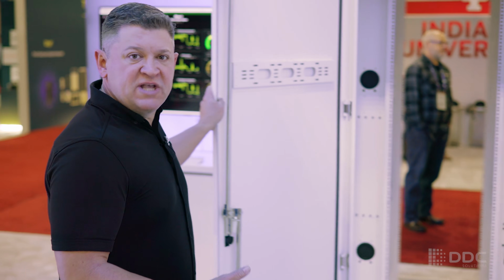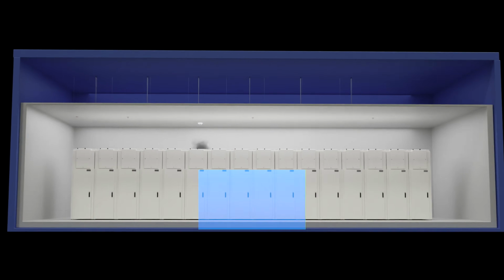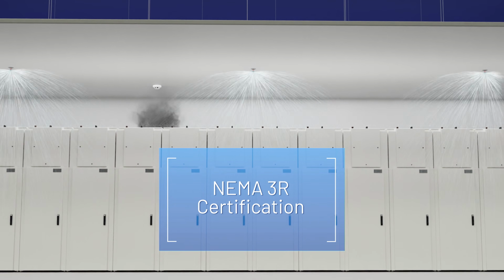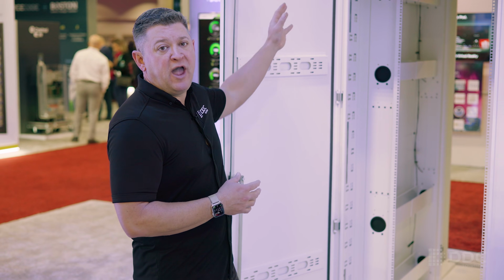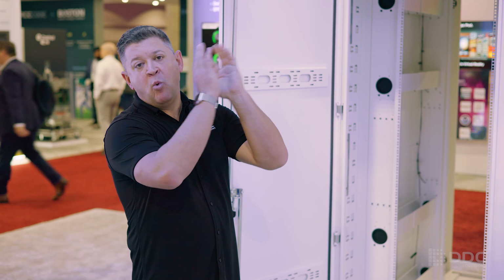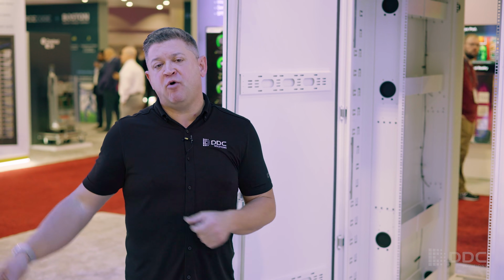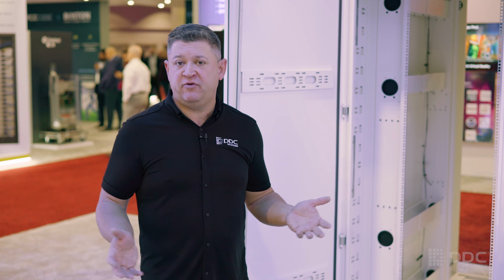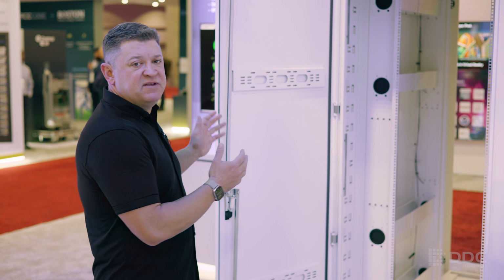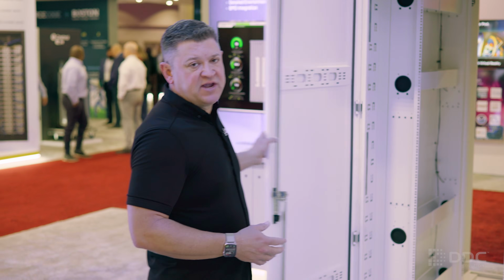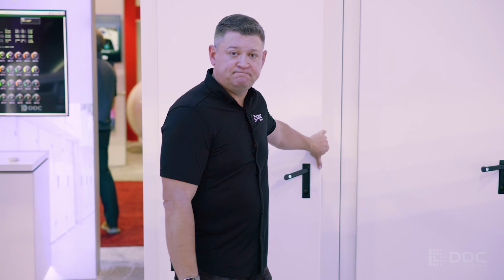We've upgraded the robustness of the cabinet so that we've got full NEMA seals around it, which is very important in today's world. As we integrate more liquid into the data center, chances of leaks or mishaps happening are very critical. While the cabinet utilizes both air and liquid to cool, surrounding water pipes and distributions of water throughout the data center do cause a threat to infrastructure. By making the cabinets NEMA 3R sealed, we now have a protective environment around all of that critical infrastructure, even if something catastrophic happens outside of the data center environment.